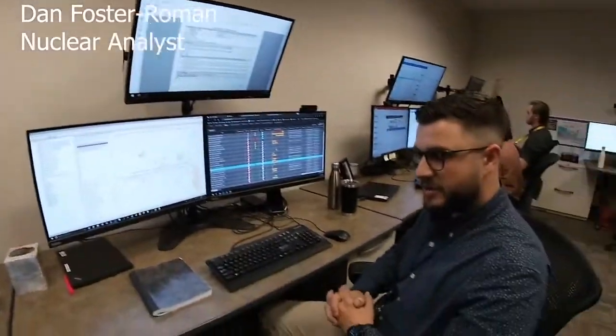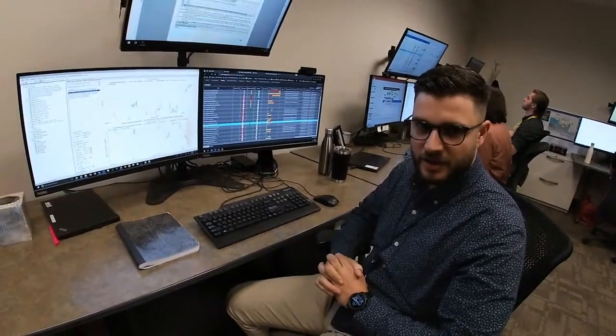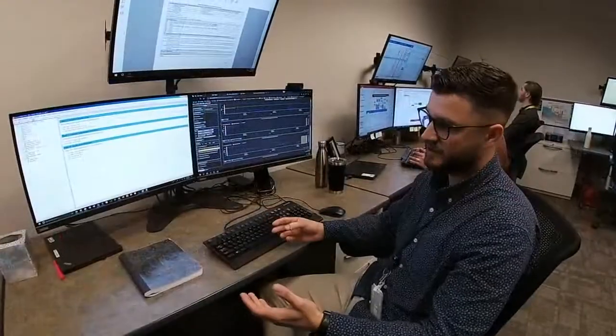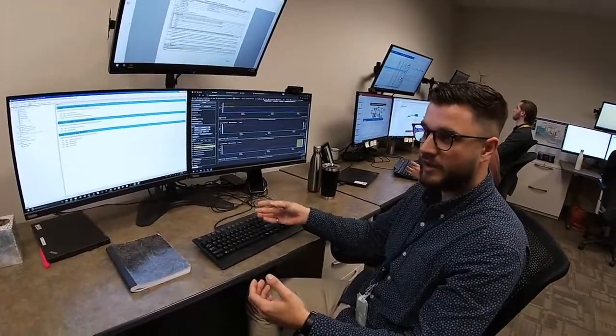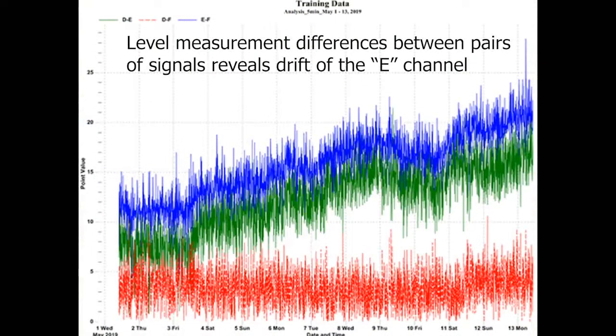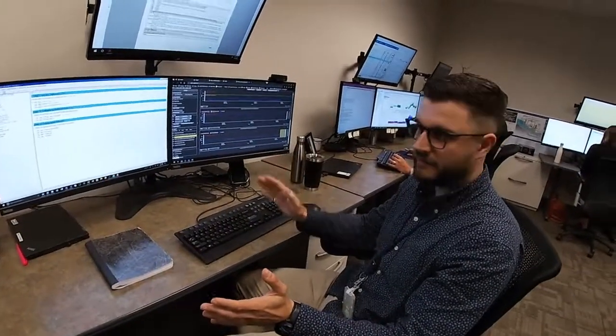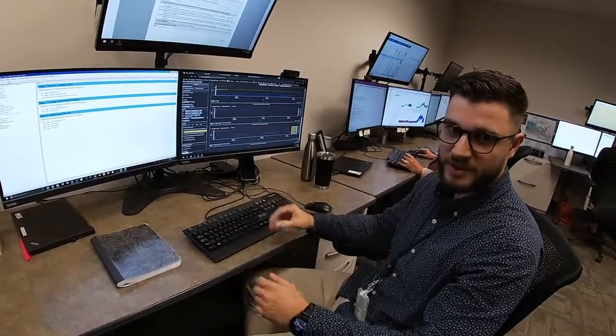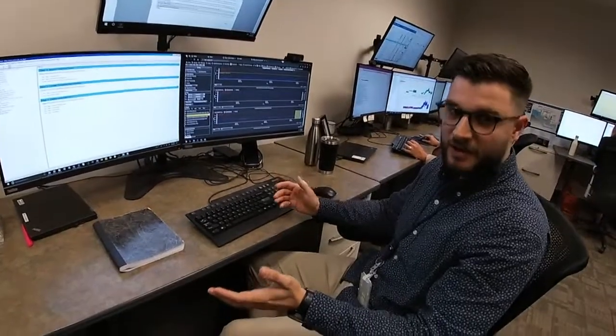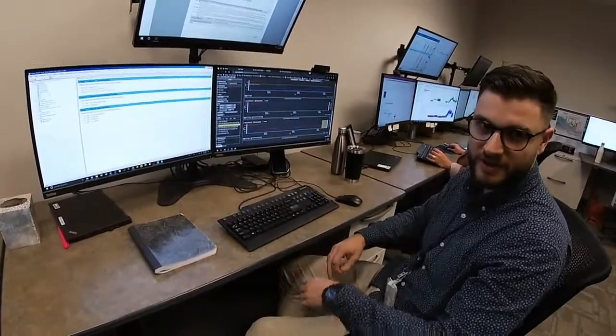So what do you do here in the M&D Centre? I'm an analyst coming from a background in performance engineering at Darlington. Our safety systems typically have triplicated sensors, so we can take advantage of that and monitor for the calibration of each of those, then identify in real time when one of them starts to drift. We looked at a 10-year history of over 5,000 preventative maintenance calibration results and found just about 1% of them actually needed to be done — so you can save a lot of maintenance resources and redirect them to higher value work.